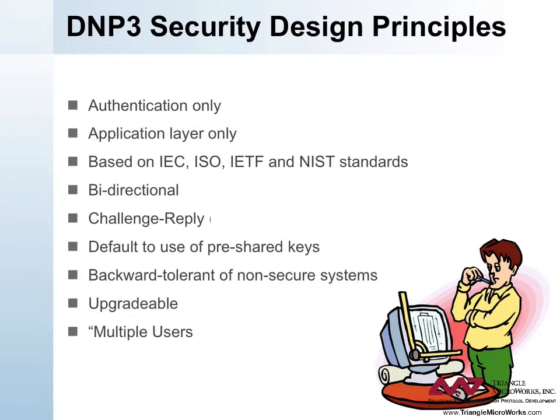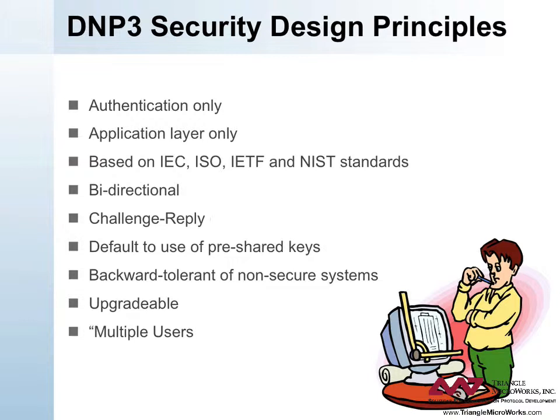Application Layer Only: DNP3 must be used over a variety of different physical networks and may be bridged from one to the other, as in the case of a TCP/IP terminal server or IP radio. Only authentication at the application layer will ensure end-to-end security. Application layer authentication also permits the possibility of protection against rogue applications that may be co-resident with the DNP3 application and attempt to use the DNP3 link without authorization. Based on standards: DNP3 Secure Authentication follows the IEC 62351-5 specification, which also applies to the IEC 60870-5 family of protocols. IEC 62351-5 makes use of various ISO, IETF, and NIST standards so that the security technology used has been well proven.